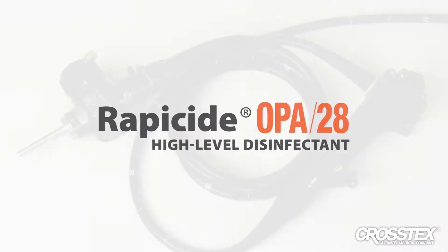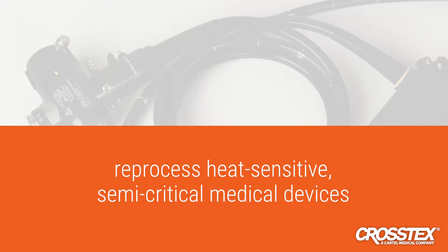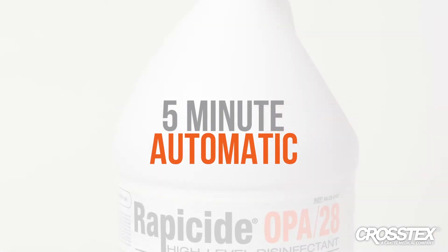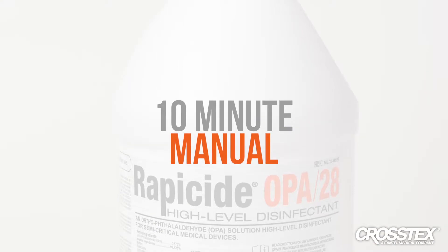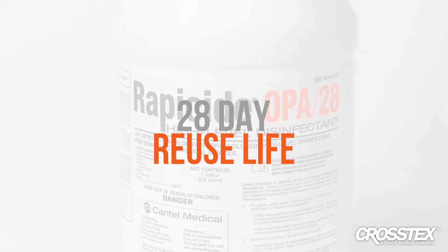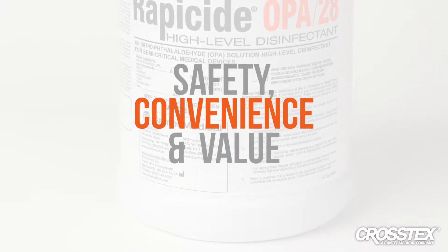Rapicide OPA/28 high-level disinfectant provides a superior way to reprocess heat-sensitive semi-critical medical devices that are unsuitable for sterilization. Rapicide OPA/28 features a 5-minute AER disinfection contact time, a 10-minute manual disinfection contact time, and a 28-day reuse life — which is twice the reuse period of 14-day OPA brands — with guaranteed materials compatibility, allowing for the ultimate combination of safety, convenience, and value.